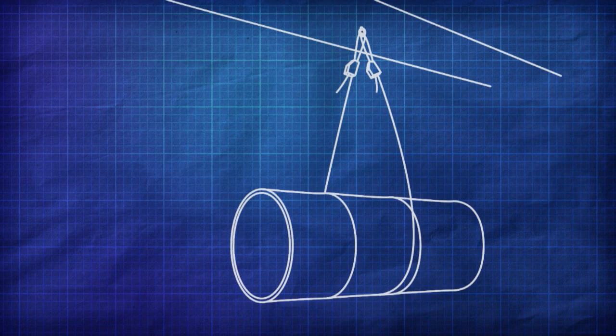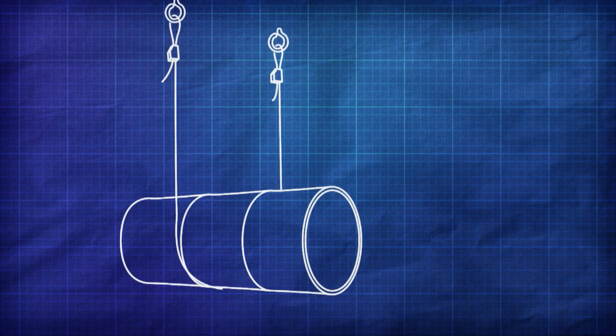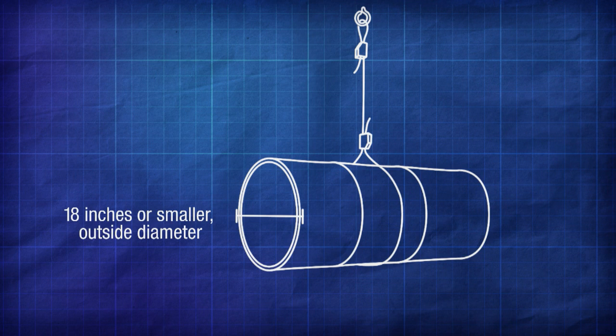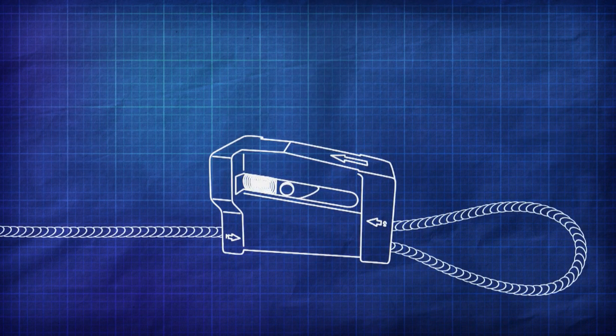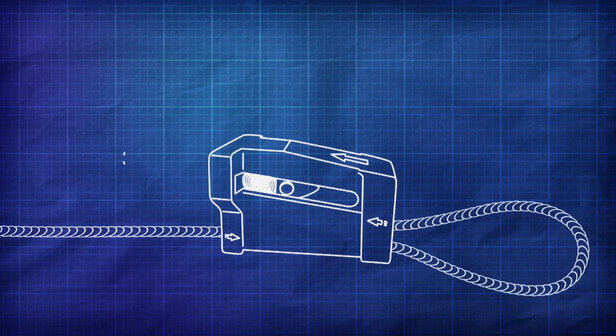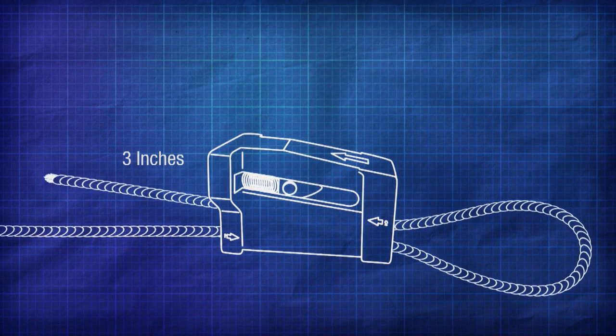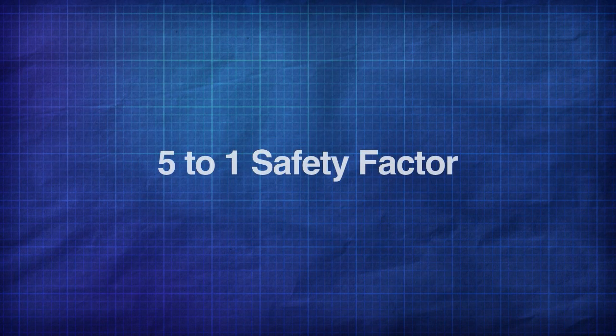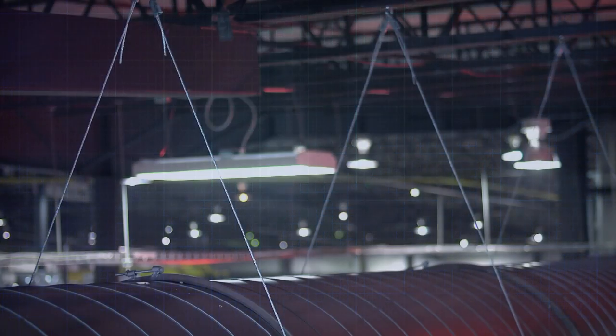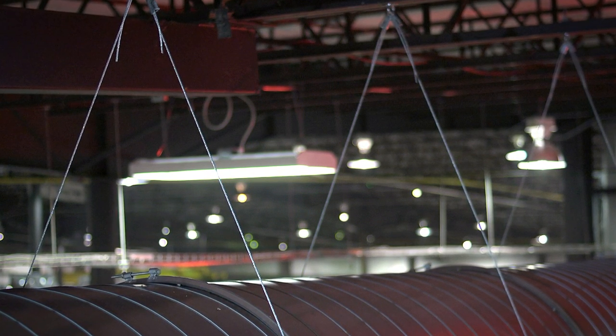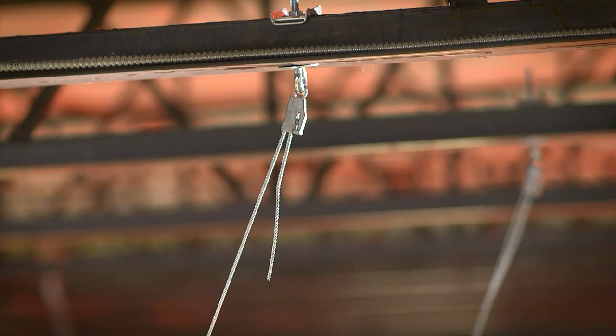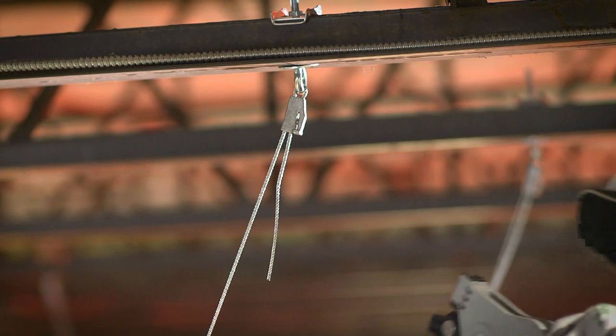In an application where movement is not expected, the single-point saddle method, the standard horseshoe method, and the standard loop may be used. No matter the configuration or weight of duct you need to hang, a 3-inch tail of steel cable must be left outside the mechanism. Each clutcher is manufactured with a 5-to-1 safety factor, designed to protect the system against a temporary increase in weight load. The working load limit should not be exceeded during operation.